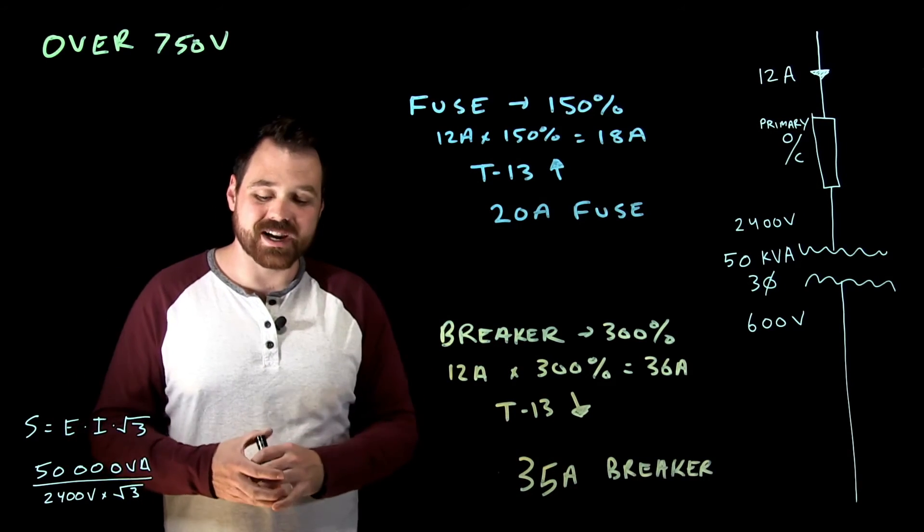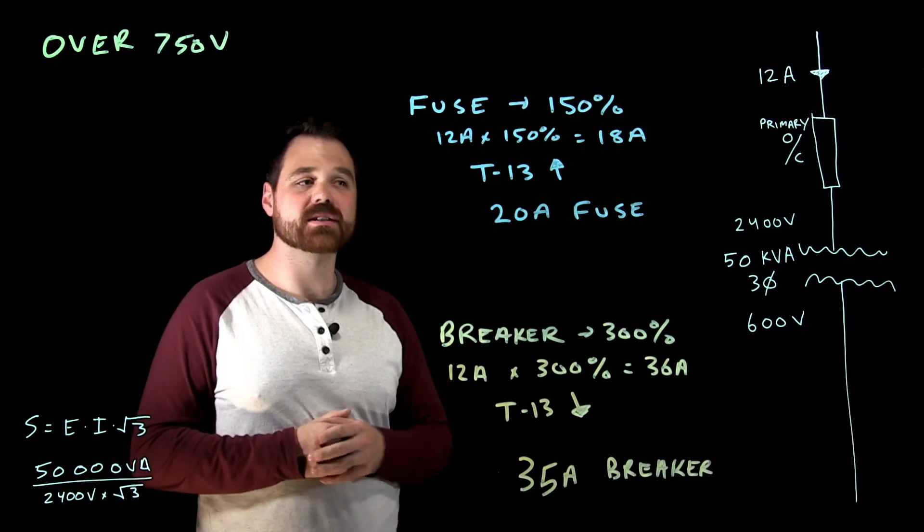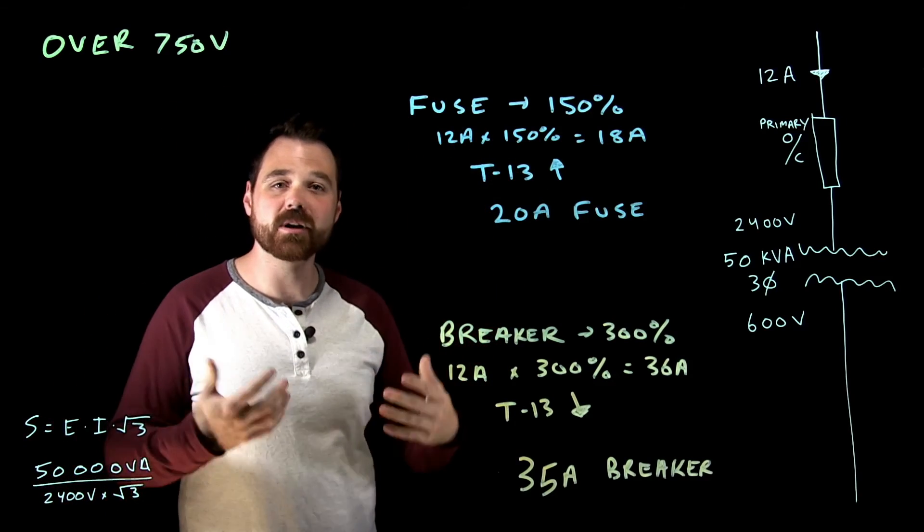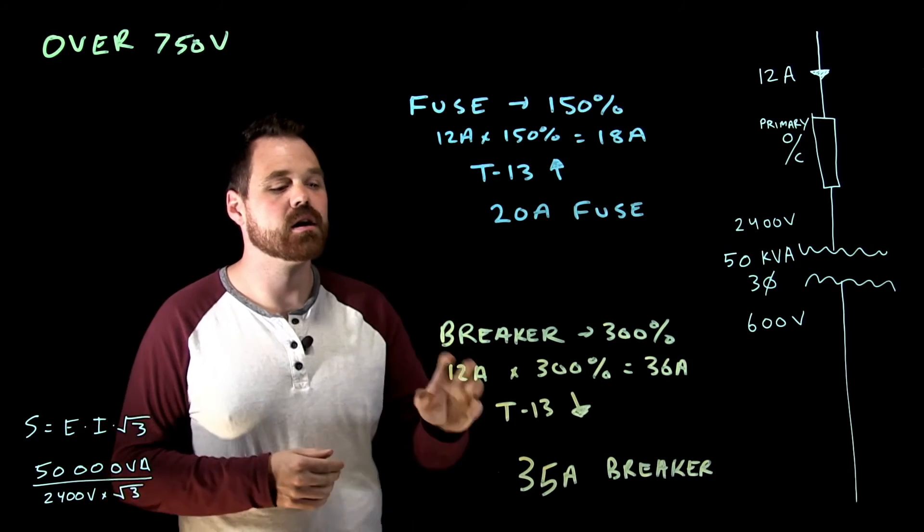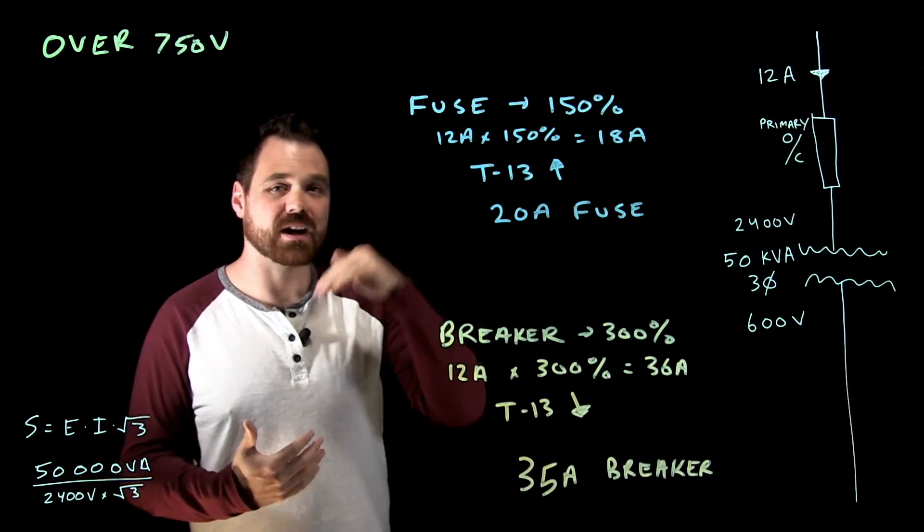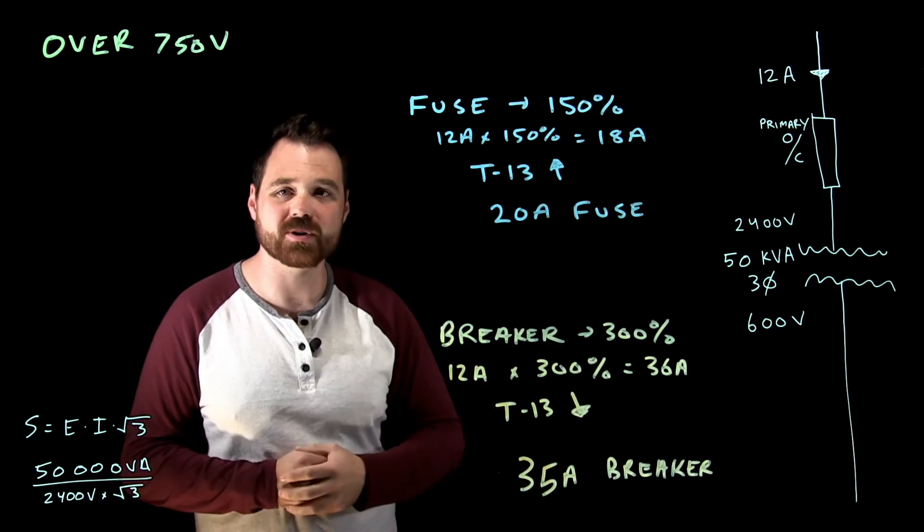So that's kind of the trick with sizing a primary overcurrent on a transformer over 750 volts. With a fuse, if that 150% is not available, I can go to the next higher size. With a circuit breaker, if that 300% is not available, I have to actually go down to a smaller size, because I cannot exceed 300%.